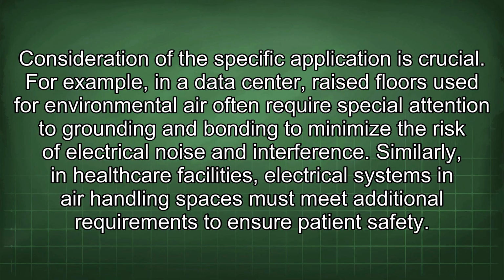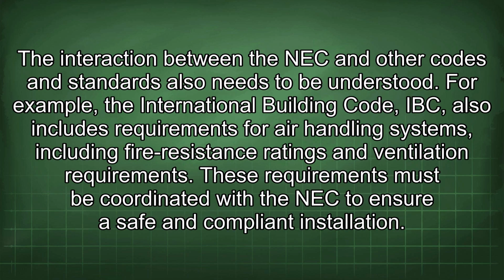For example, in a data center, raised floors used for environmental air often require special attention to grounding and bonding to minimize the risk of electrical noise and interference. Similarly, in healthcare facilities, electrical systems in air handling spaces must meet additional requirements to ensure patient safety. The interaction between the NEC and other codes and standards also needs to be understood. For example, the International Building Code (IBC) also includes requirements for air handling systems, including fire resistance ratings and ventilation requirements.